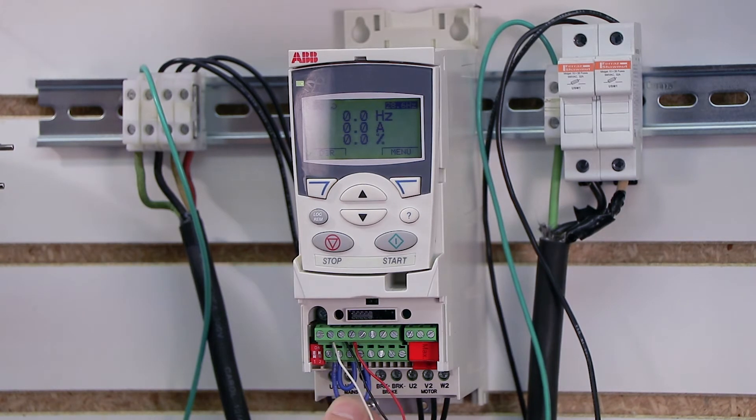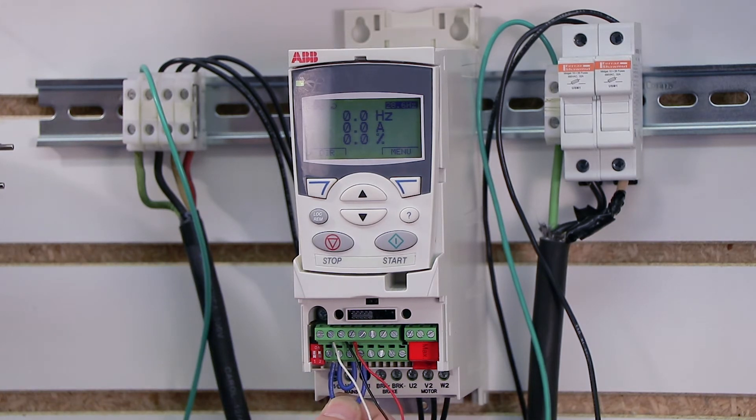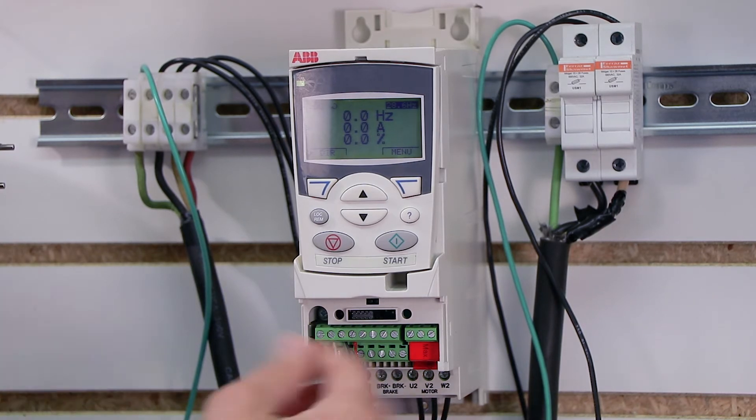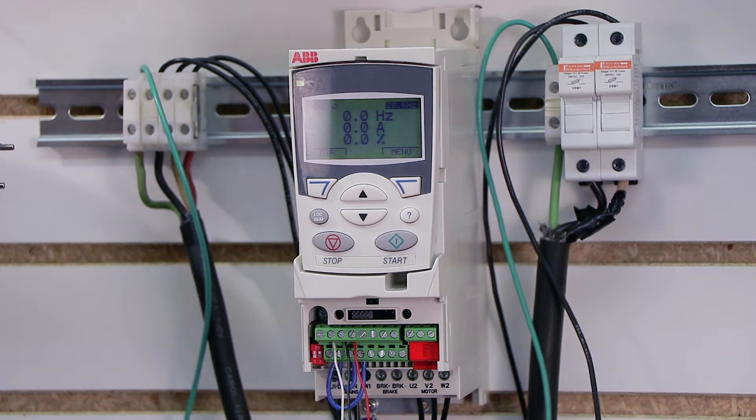Now this is the jumper we're going to replace with an external push button in the next video to start the drive from an actual push button instead of a jumper. But for the sake of this video, like I said, we're just jumpering our start command so that we can start the drive with the terminal strip and then run it off the speed pot.